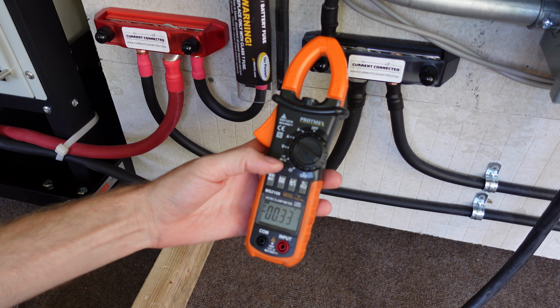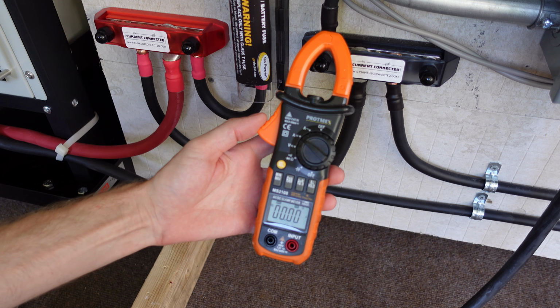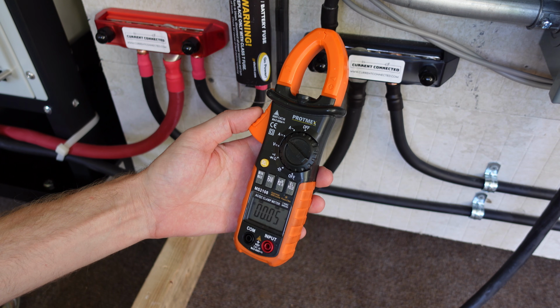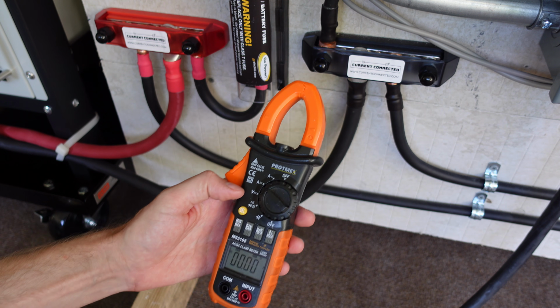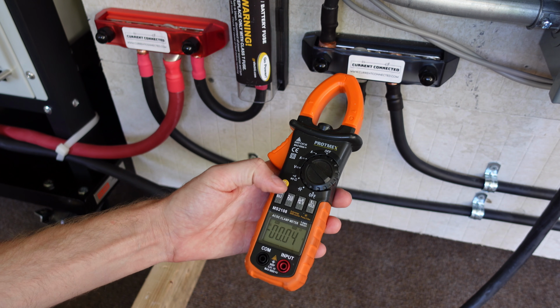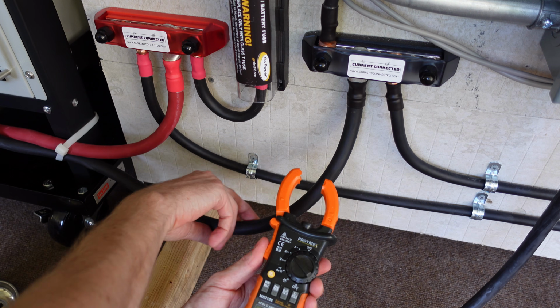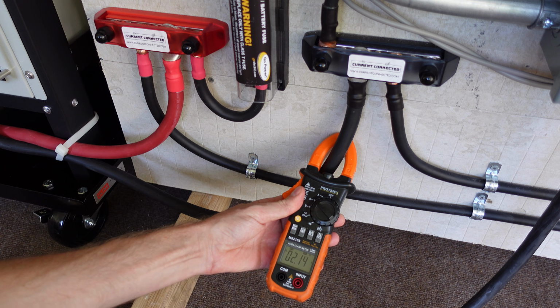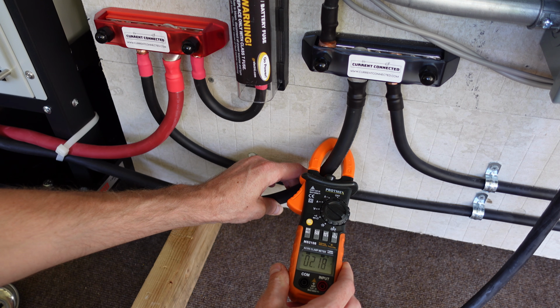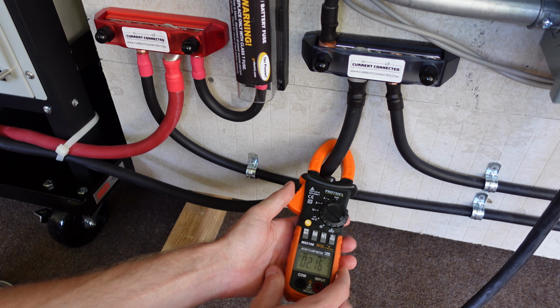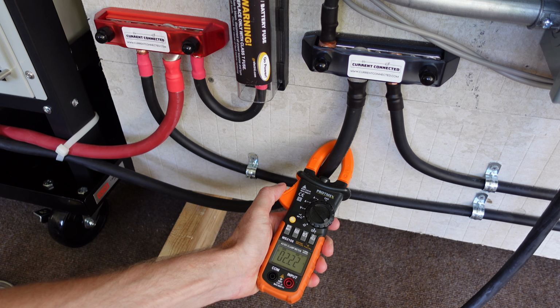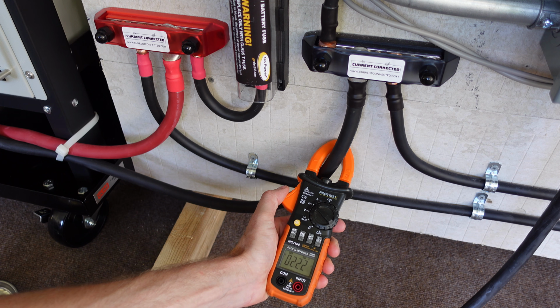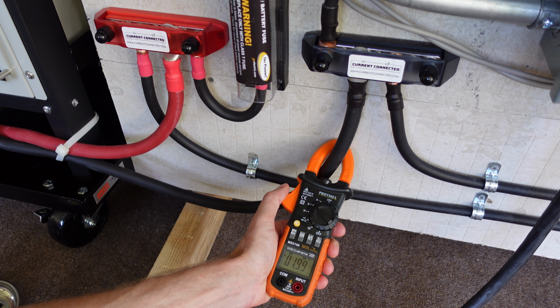Alright, so I want to check the idle consumption of these inverters. They are both running in split phase mode with no load on. So I've got my clamp meter on amps and I've got it zeroed out there. So I'm seeing approximately 2.2 amps, which is not too bad at all. That's roughly, what, 110, 120 watts. It's pretty good for 2 large inverters like this.